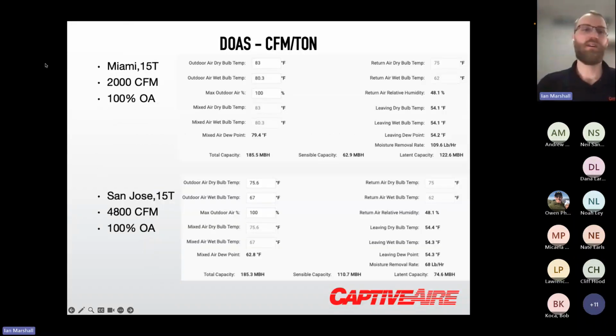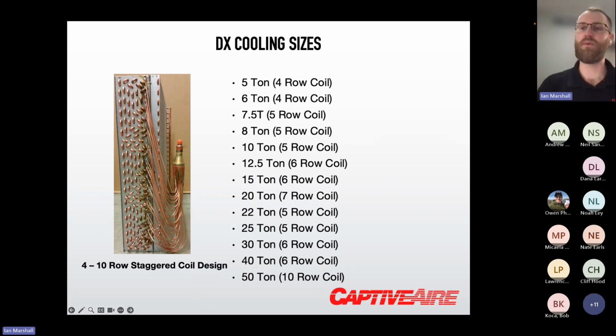just to make sure we're on the same page with equipment sizing. So this is a very quick example of a 15-ton unit that I ran a selection for in Miami, and then a 15-ton unit that I ran a selection for in San Jose, California. Obviously, Miami is very hot and humid. San Jose is much drier, a little bit more mild climate. So that 15-ton unit in Miami at the ASHRAE design conditions, to hit around a 54 to 55 degree leaving air temperature off the coil, was running at 2,000 CFM at 100% outside air. That same 15-ton unit at 100% outside air, to hit the same leaving air temperature with San Jose weather, was running 4,800 CFM. So obviously a huge difference in airflow and design just based on location. That's why we'll pry for that location information on each selection we work up.